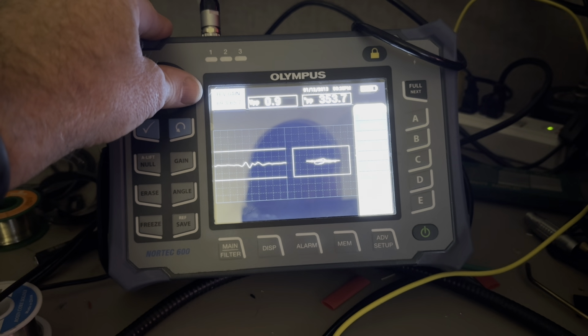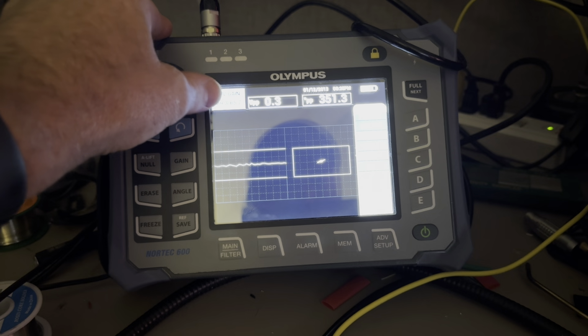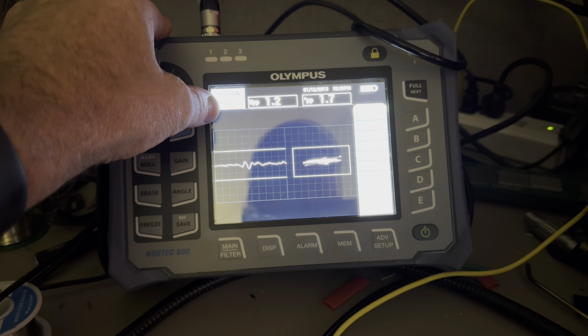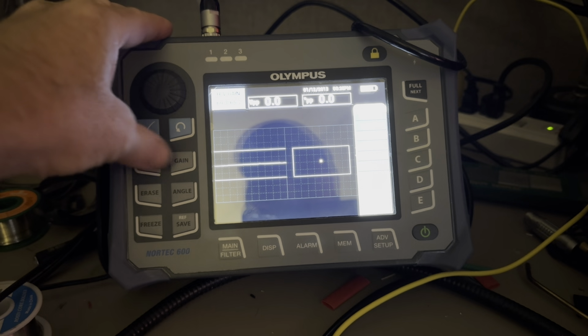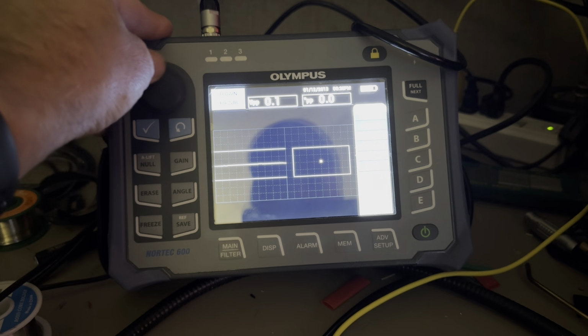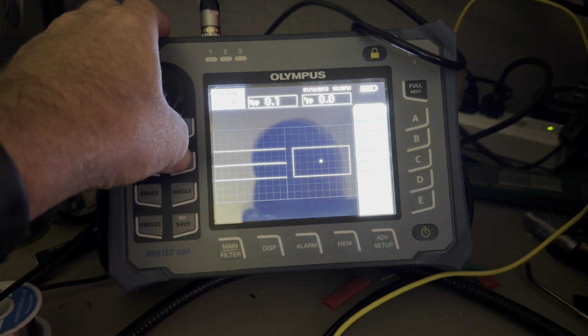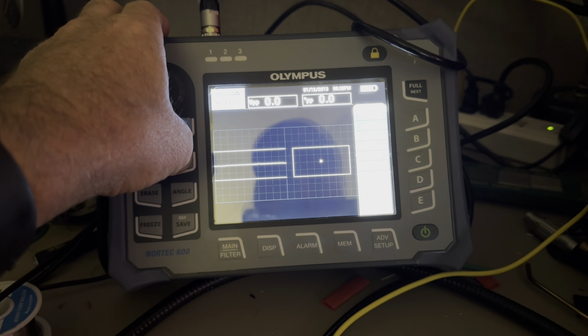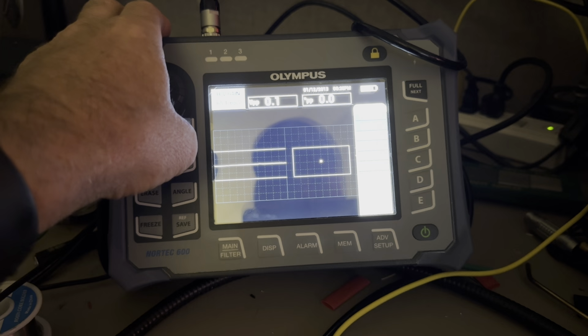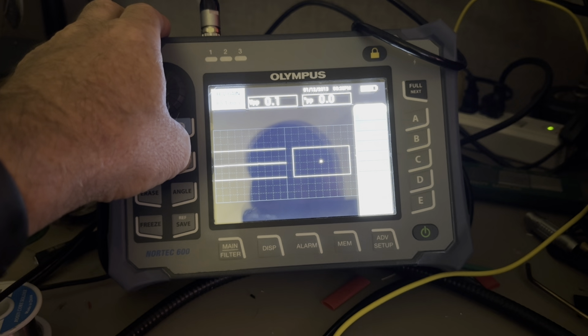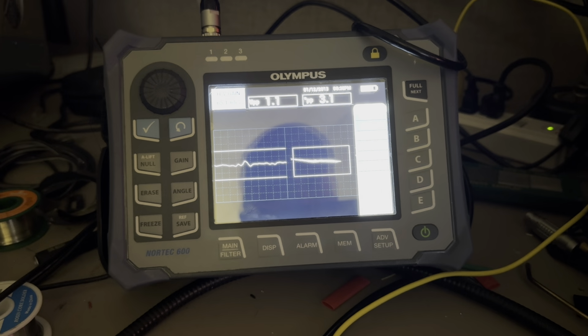That looks good. Now here I can see my horizontal gain is higher than my vertical gain. I don't want that. So I'm gonna hit the gain, bring it down. Let's see, so 65.7 for vertical, 61.5 for horizontal. So I'm gonna leave it like that because there my vertical gain's a little bit hotter. And that's gonna give us a little more vertical when we come to a flaw. So that's right in the center of my hole with no flaw, no action on the sweep display. The only action in our Lissajous is horizontal.